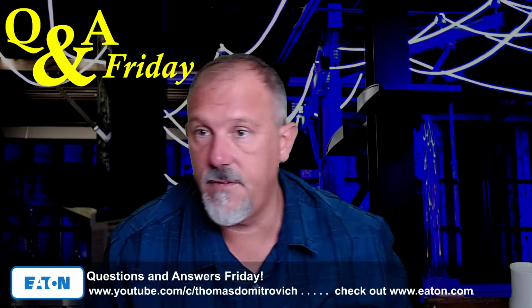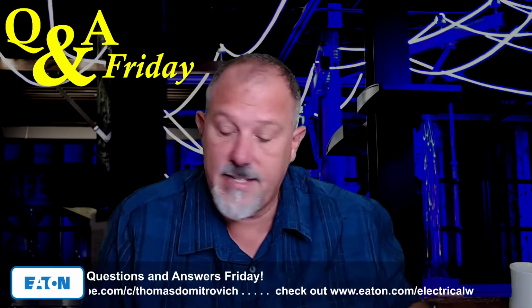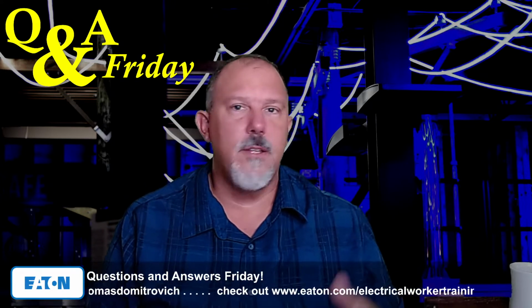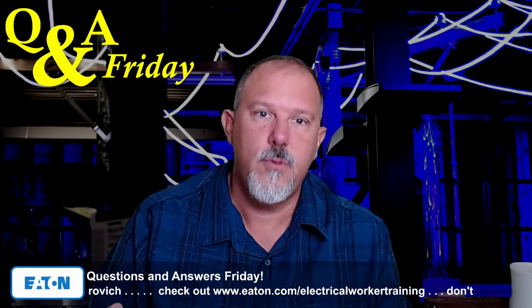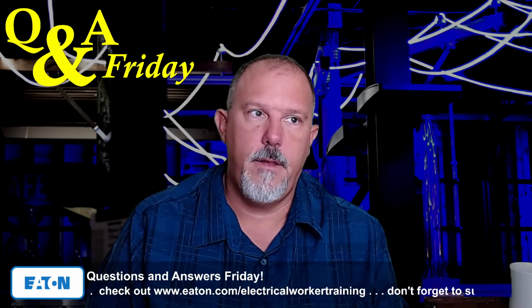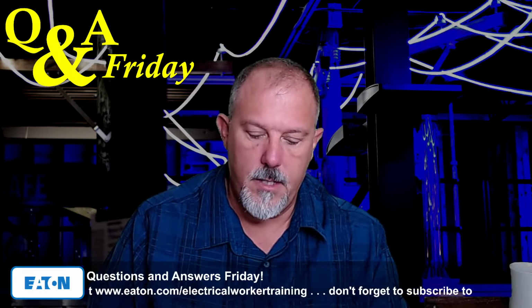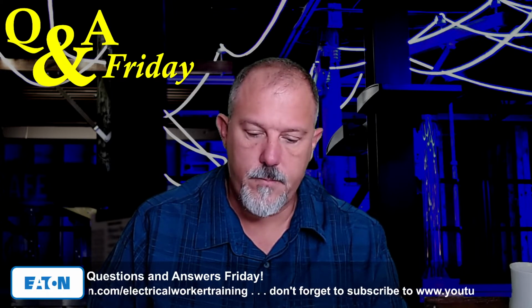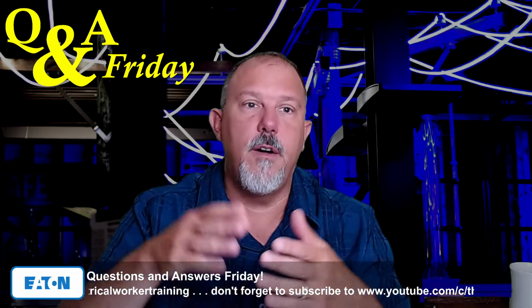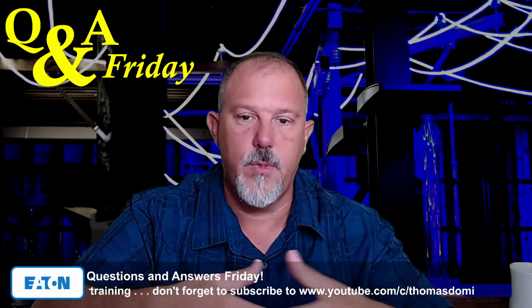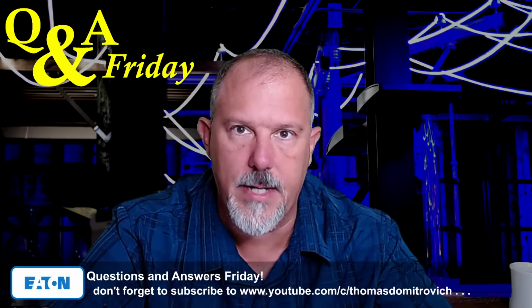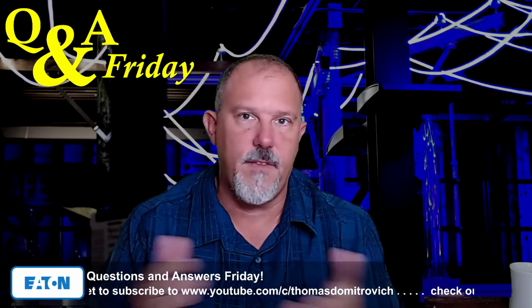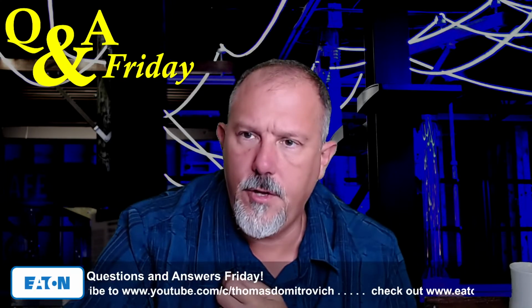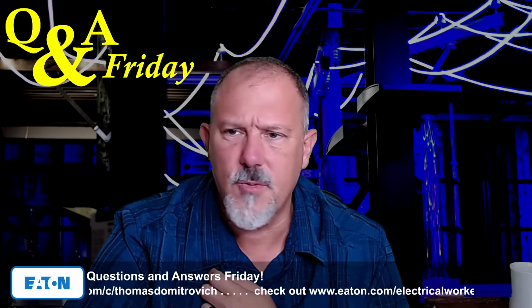There's no exceptions that says anything about if you sized it for... SCCR is not overcurrent protection. SCCR is equipment protection, and SCCR is about the ability of a piece of equipment to withstand letting current pass through it. That's not related to arc flash. And you brought up SCCR, and then you brought up locked rotor.